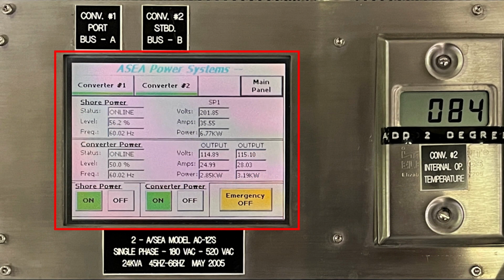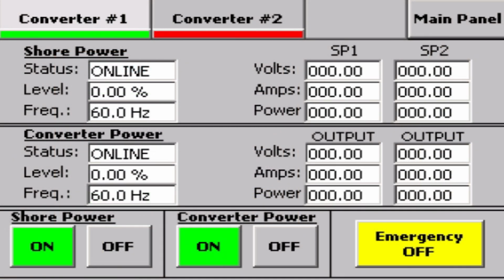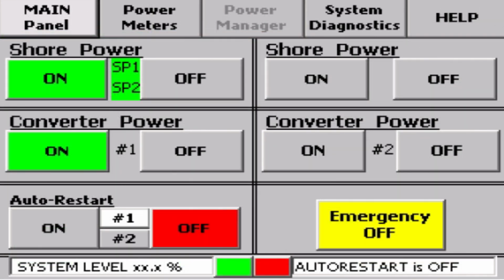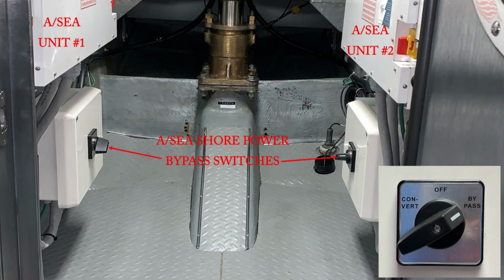Most frequency converters are also available with remote display panels in case the units are located in spaces that are difficult to access. Second, with either isolation transformers or converters, it's always a good idea to install rotary bypass switches so these units can be bypassed in case of a failure.